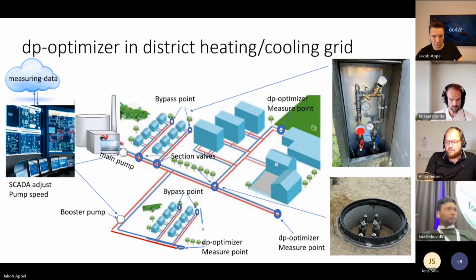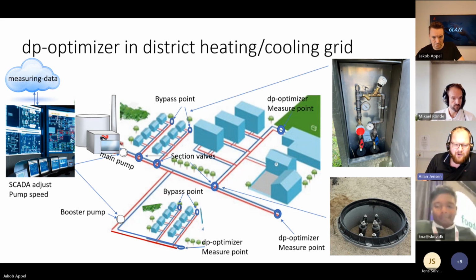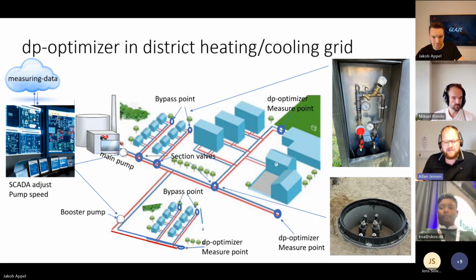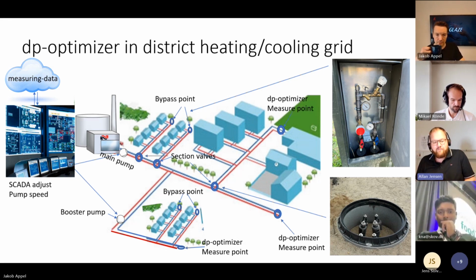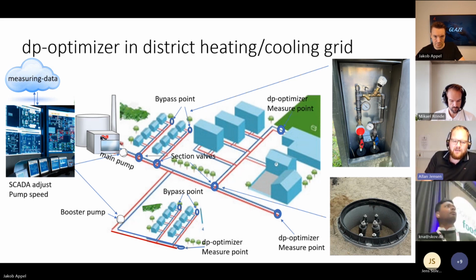And when we're lowering the pressure, we also reduce leaks in pipes, and we also reduce pipe loss. And the other thing we can see is the bypass point. The pipes in district heating are dimensioned for winter, but in the summer times the pipe is too big, and if we don't have bypasses, there are two possibilities. We can do as we used to do, which is to have a high temperature, but the future points in the other direction. We are lowering the temperatures in district heating, so by that we need a bypass point.